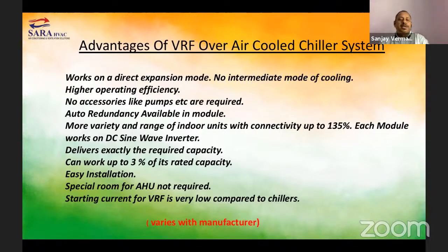It delivers exactly the required capacity. This can work at 3% of its rated capacity, easy in installation. Special room for AHU not required for this because we are using the smaller indoor units for the conditioned area. Starting current for VRF is very low compared to chillers.